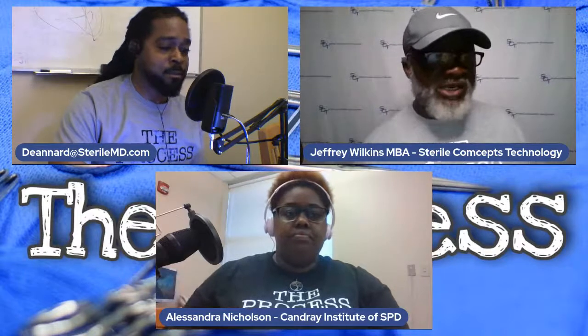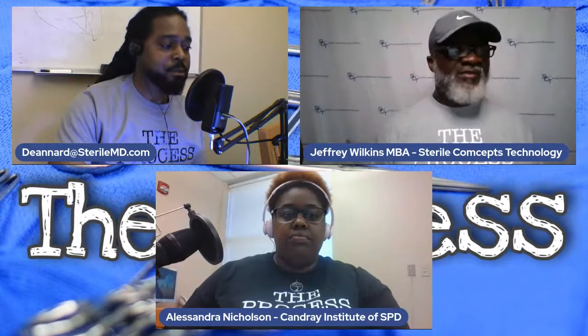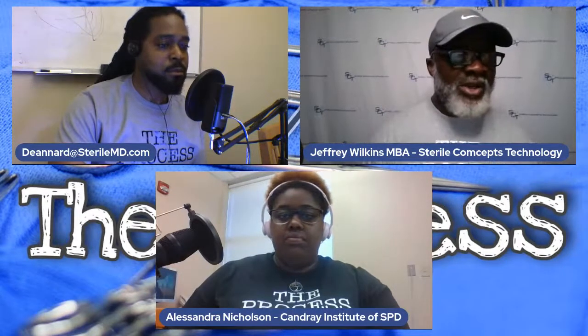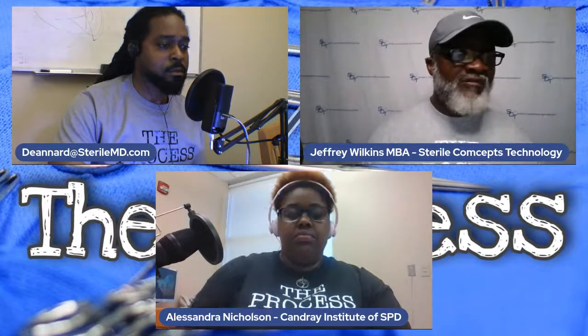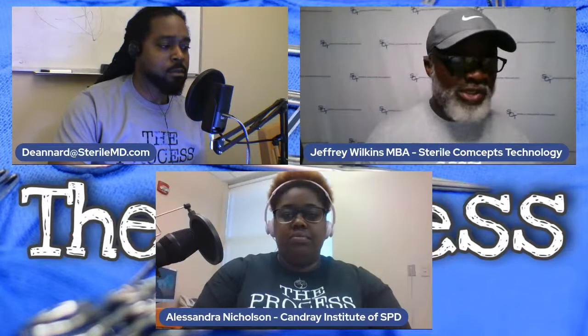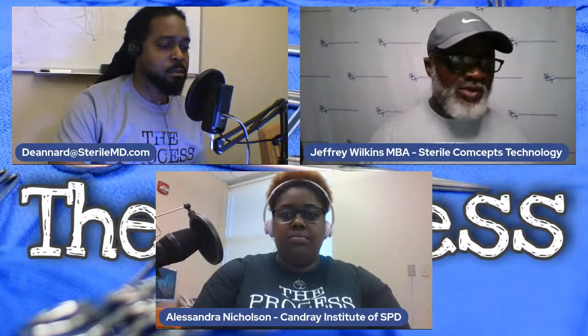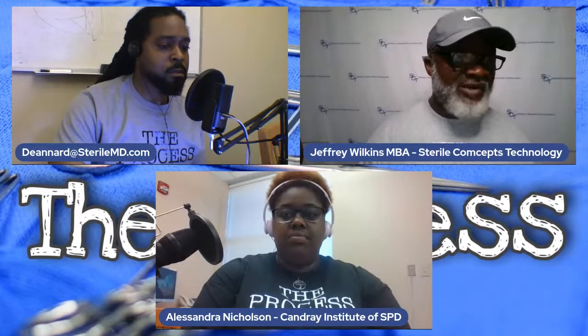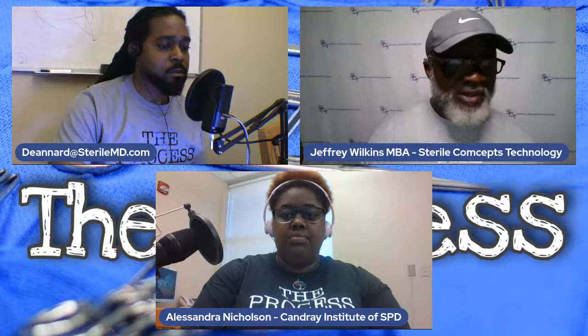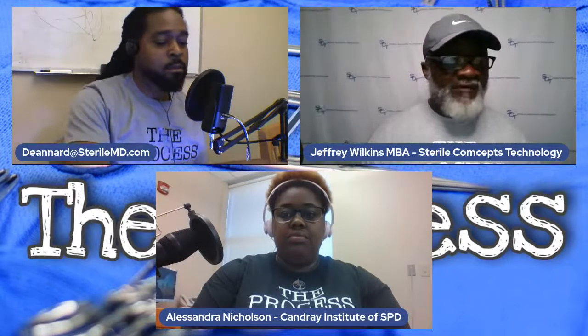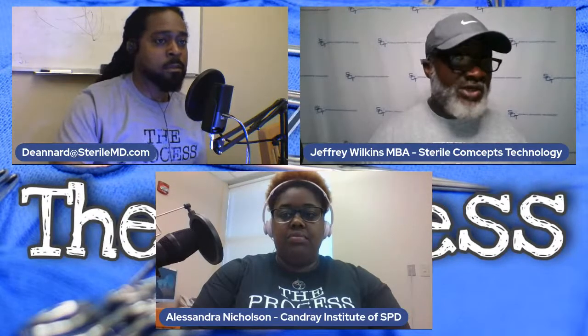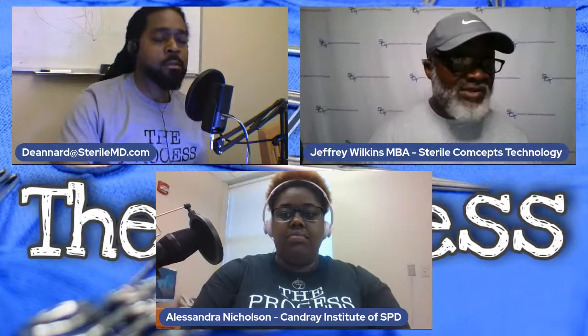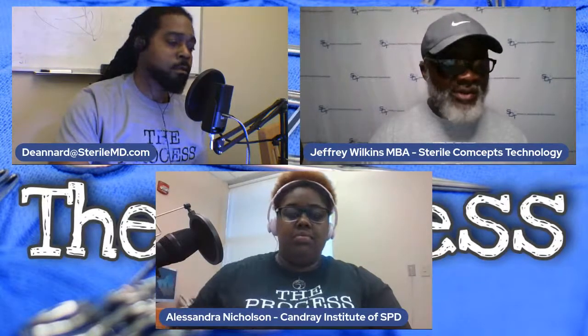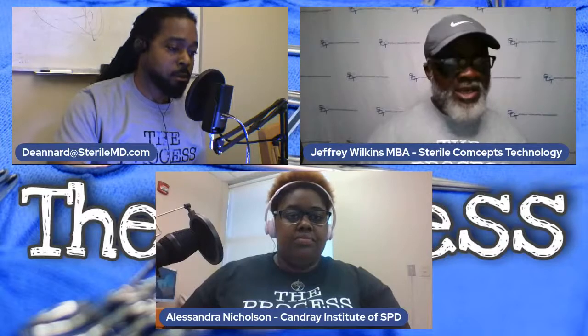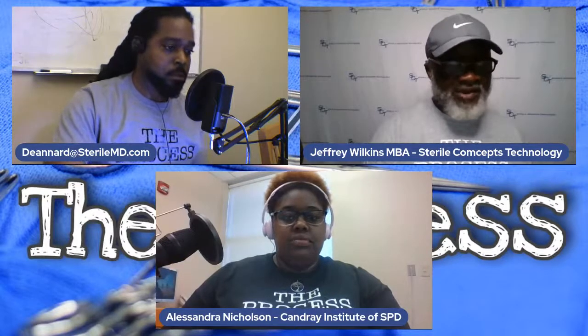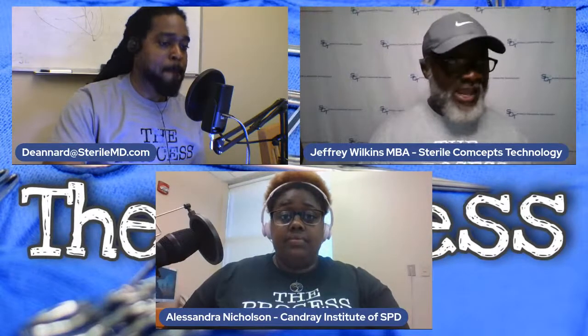Well, on the technician level, if you have an incomplete IFU, you want to reach out to your supervisor or manager to explain to them that you don't have all the information necessary to process what you're trying to do, and there's some confusion or some ambiguities that you have to have clarified. If you're on a supervisor level and you see the incomplete IFU, then you should take the moment to see if you can research it and get the latest one. If not, you should reach out to the device manufacturer, your rep, so that you can get that information, and then you have to educate all your team, and that's three different teams for different shifts. Then that's what you have to do.